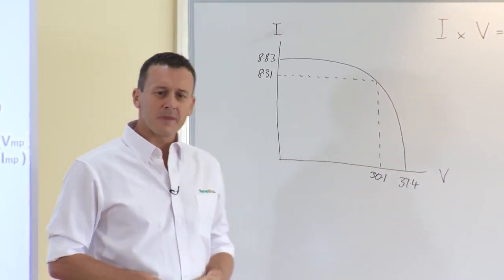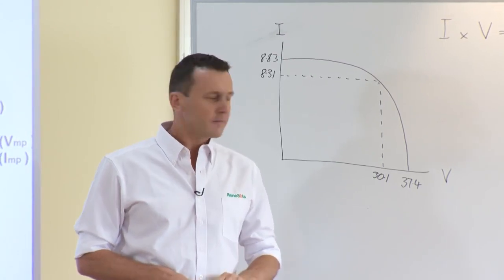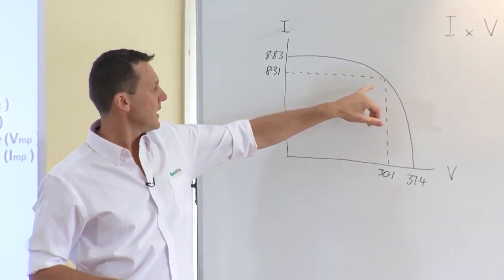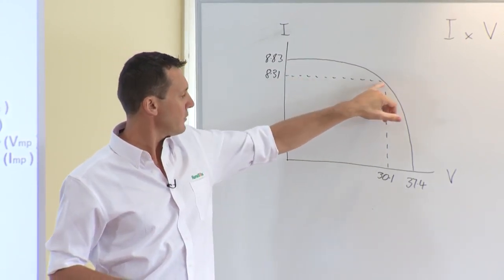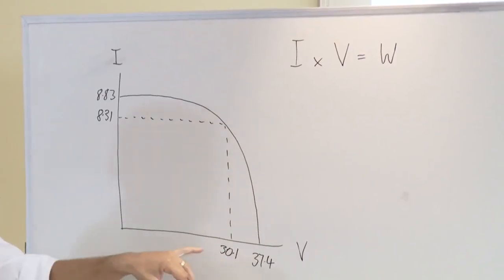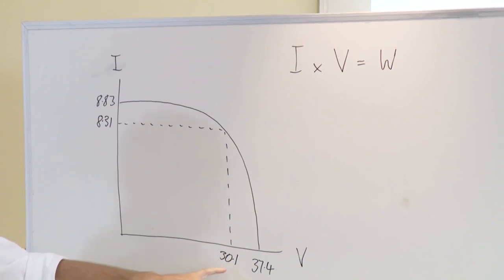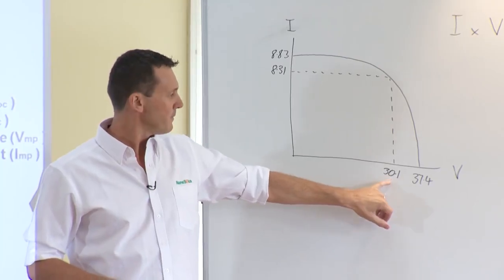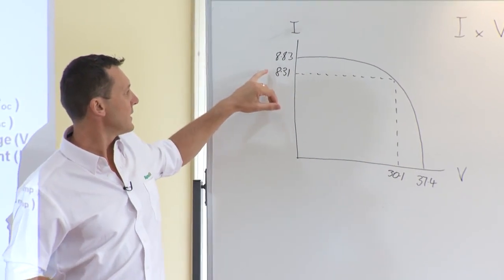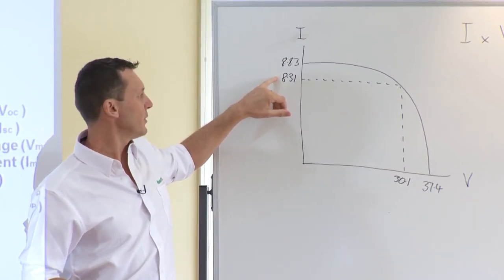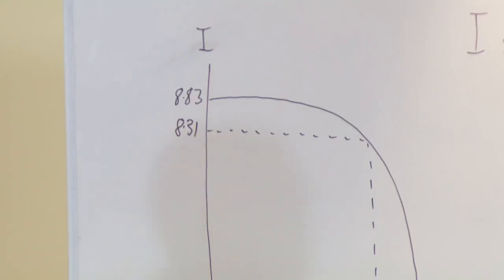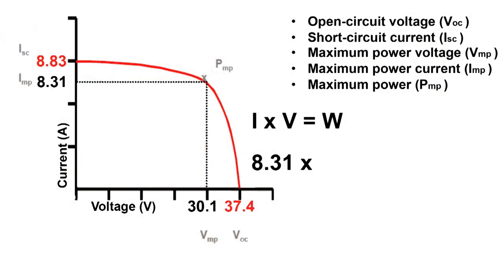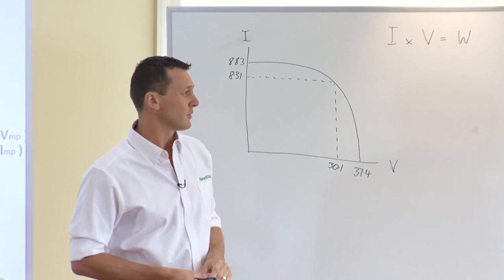So if we look at the maximum power point figures for that panel, it's drawing a graph like this where we can see the P max position for the voltage is 30.1 volts, and for the current the maximum is 8.31 amps. So if we use this formula up here and we multiply 8.31 by that 30.1 volts, then that will actually give us 250 watts. And that's where that maximum capacity of that panel comes into play.